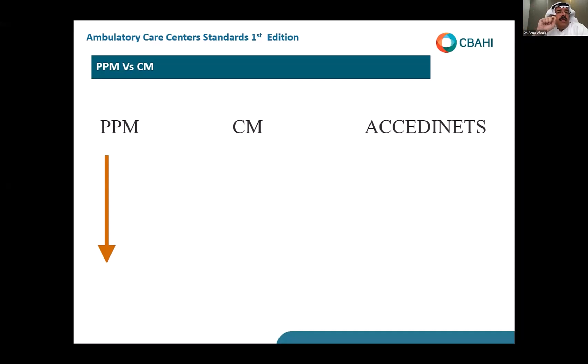PPM is preventive planned maintenance, or preventive periodical maintenance, meaning الصيانة الدورية: you do the maintenance before the defect or fault happens. You do a PPM, depending on the manufacturer requirement, every 3 months or 1 month, depending on the kind of equipment, but you need to do it properly according to the manufacturer requirement. Because whenever you have a lower PPM, you will have corrective maintenance. Corrective maintenance is when something went down and you go to repair it. However, whenever you have higher corrective maintenance than PPM, you will have accidents.